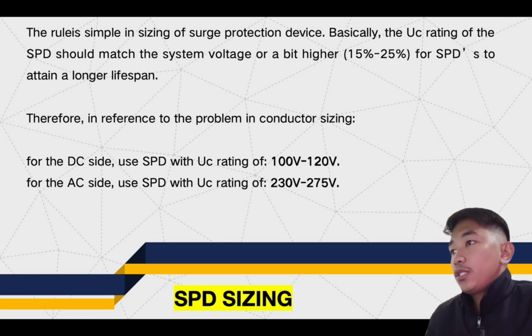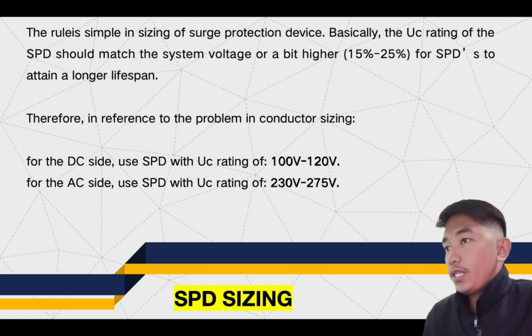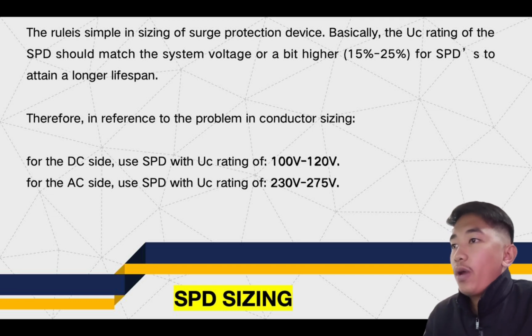So therefore, in reference to the problem in conductor sizing, on our DC side, the SPD should have a UC rating between 100 volts to 120 volts, which allows it to properly protect the system from the voltage surge while ensuring that the SPD can handle surge without being prematurely worn out. On our AC side, the SPD should have a UC rating between 230 volts to 275 volts, which aligns with the common operating voltage for AC systems and provides the necessary protection from surge while also prolonging the lifespan of the device. This approach allows for effective protection while ensuring the SPDs operate efficiently over time, reducing the likelihood of frequent replacements or failures due to the excessive surge condition.